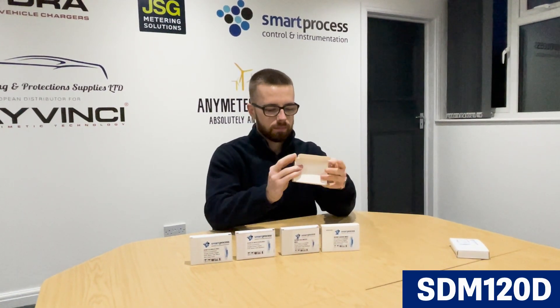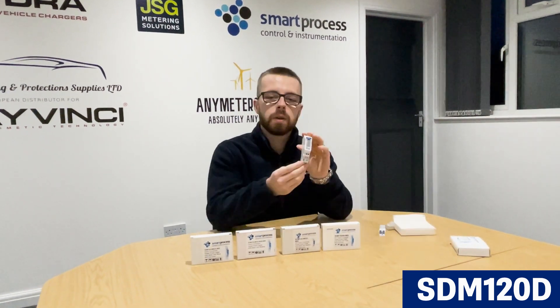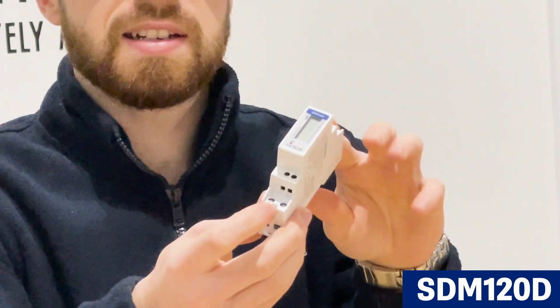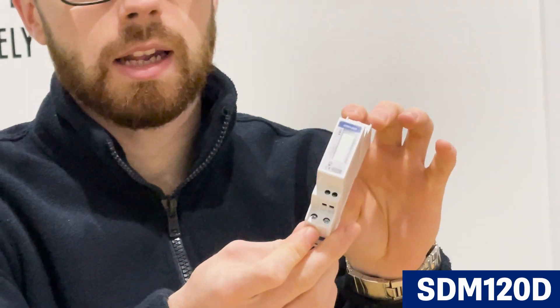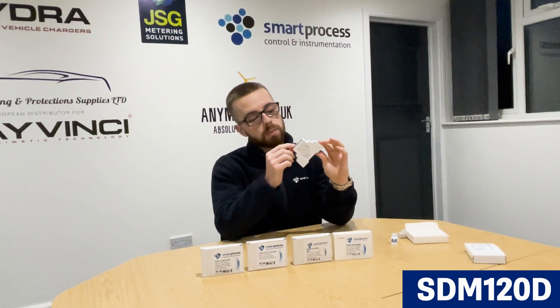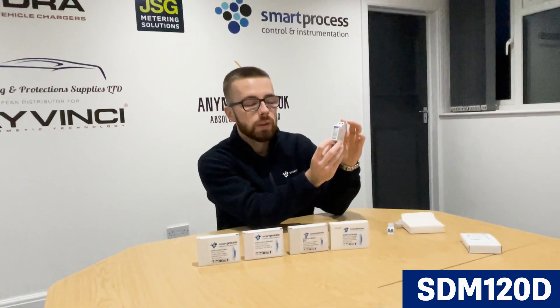The SDM120D, which is essentially the digital version of the SDM120A, is the same single module, DIN rail mounted, as per the rest of the series. This is also 45A as per the rest of the series, other than the CT operated versions. This one's got a digital display, no buttons — just a kilowatt hour check meter. It's got a pulse output on there.